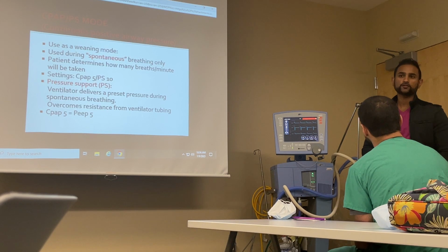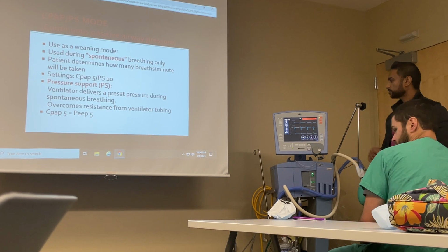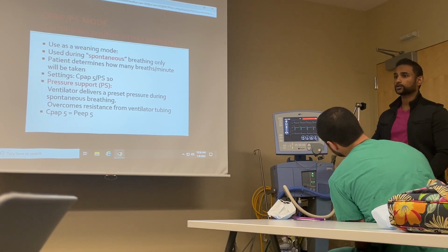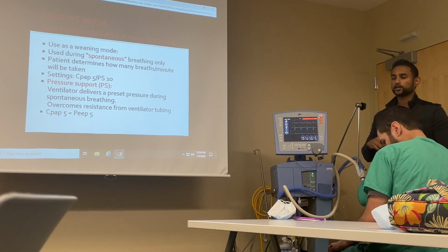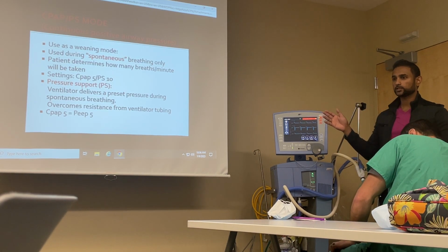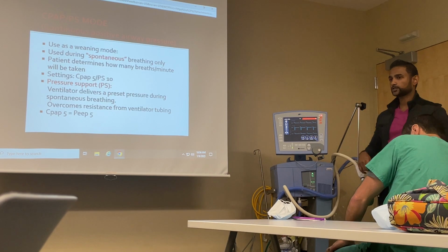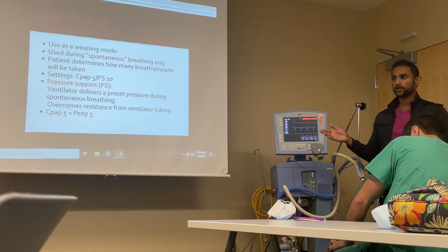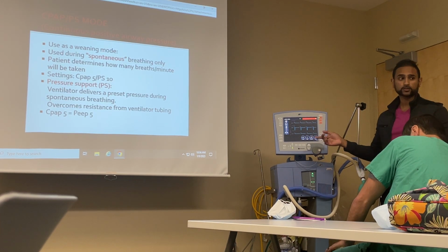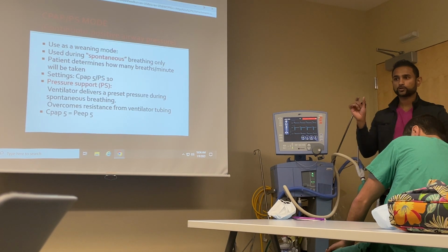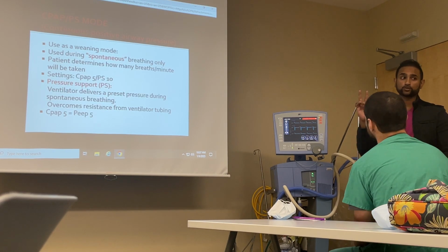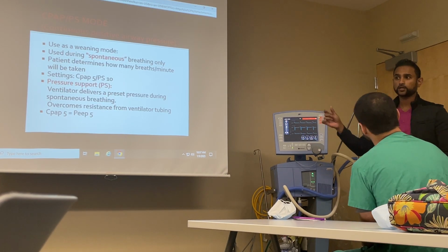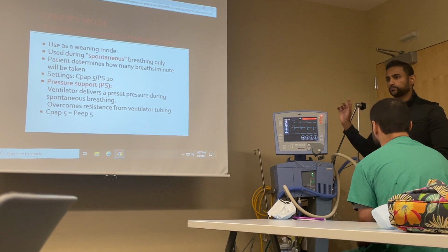Fail-safe mode, default. Yes, it automatically kicks in, because you're in another patient's room, sedating this patient with ETOH or whatever, your next-door patient is going apneic, everybody's busy, nobody can keep an eye. Can you imagine this patient going apneic? So when does the apnea alarm trigger? When you don't breathe for how long? Like 8 seconds? 20 seconds. So if you have 2 or more episodes of apnea, like 20, 20, 20, then automatically it's a failed attempt to put them back on.